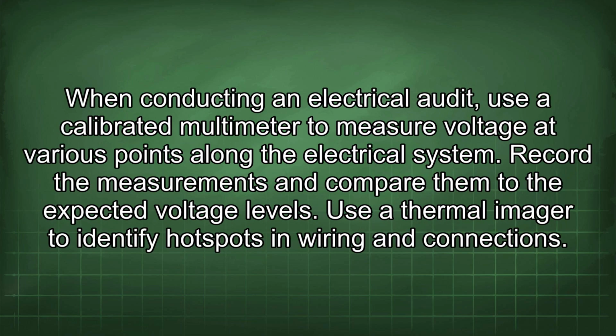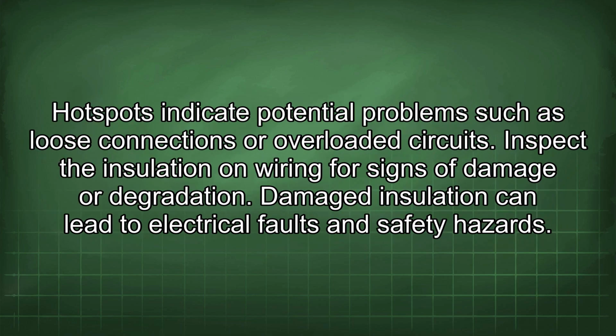When conducting an electrical audit, use a calibrated multimeter to measure voltage at various points along the electrical system. Record the measurements and compare them to the expected voltage levels. Use a thermal imager to identify hotspots in wiring and connections. Hotspots indicate potential problems such as loose connections or overloaded circuits. Inspect the insulation on wiring for signs of damage or degradation. Damaged insulation can lead to electrical faults and safety hazards.